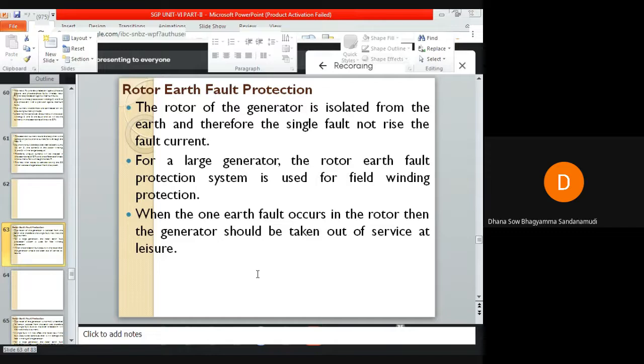So when one earth fault occurs in the rotor, it is not necessary that the system is completely tripped. Only the relay indicates that the fault has occurred, so that the generator can be taken out of service at leisure. If the fault occurs in the rotor of a large machine and persists for a longer duration, then the circuit breaker will trip, since we are providing the earth fault protection here, and the generator is to be taken out of service.